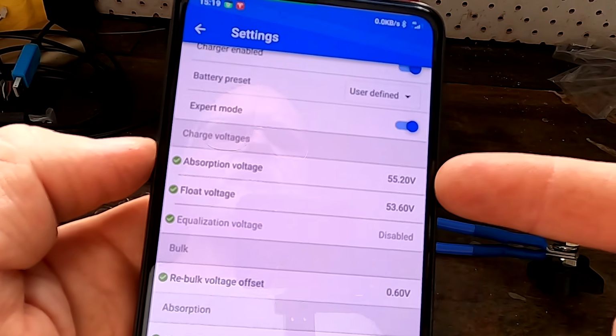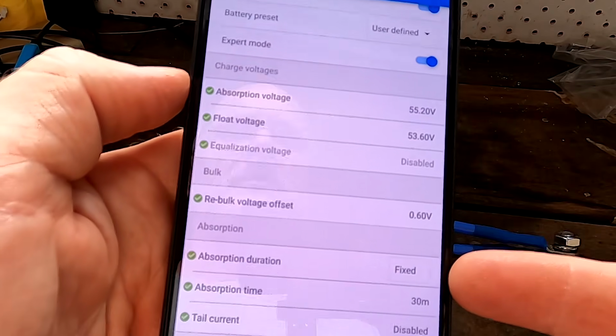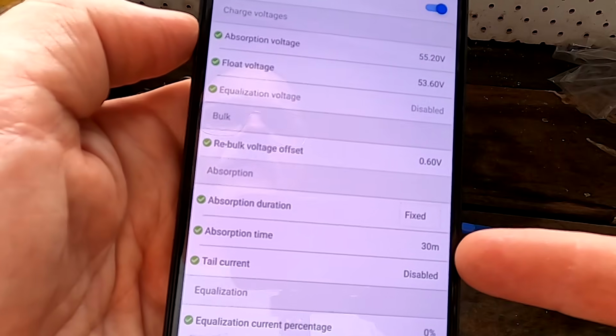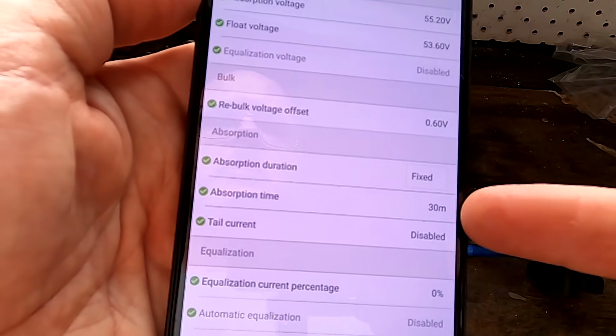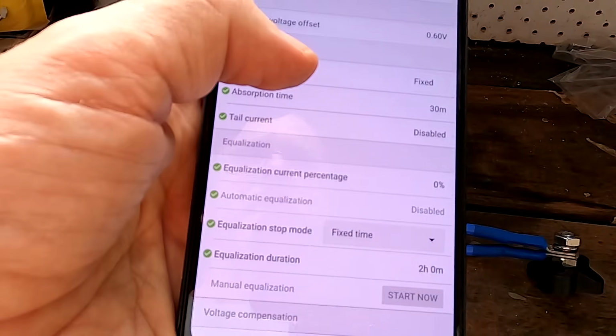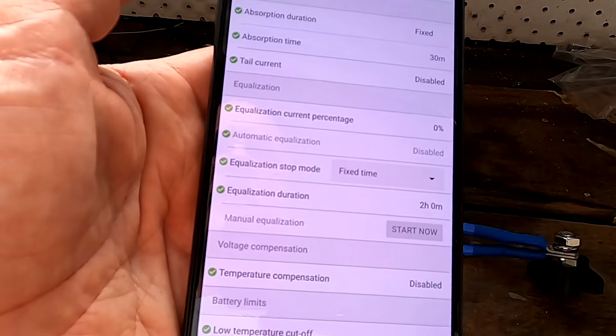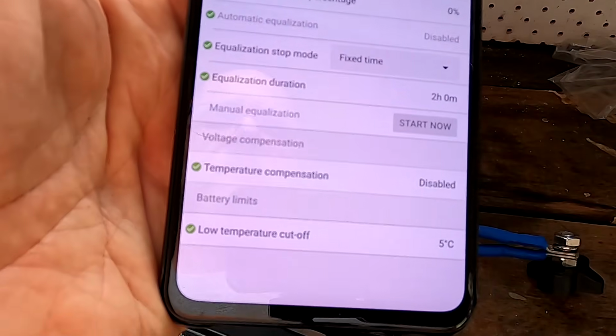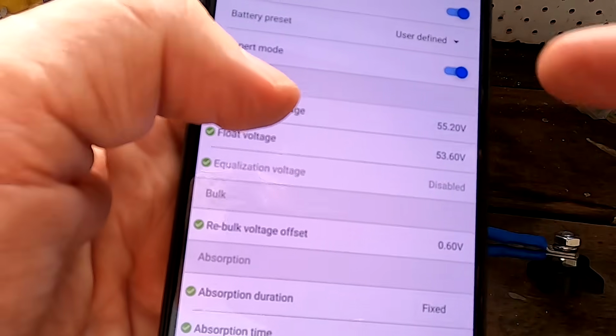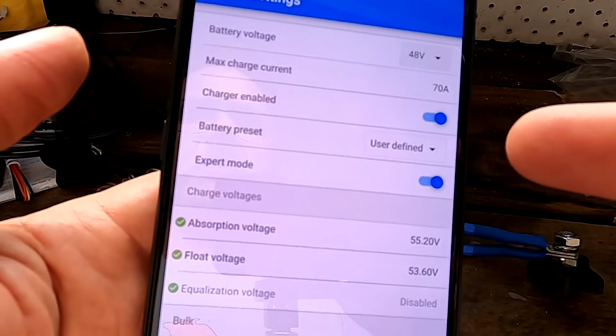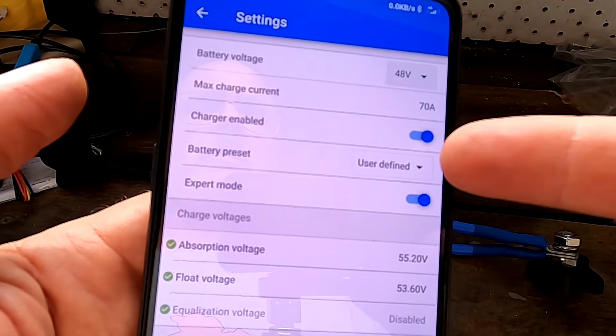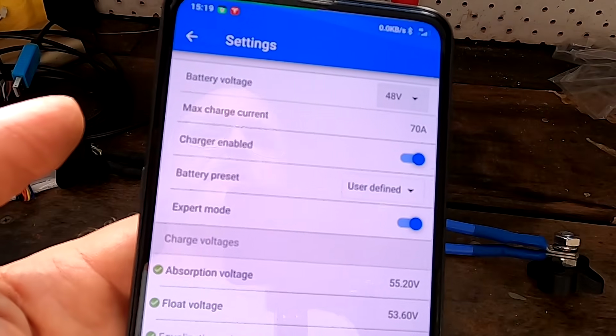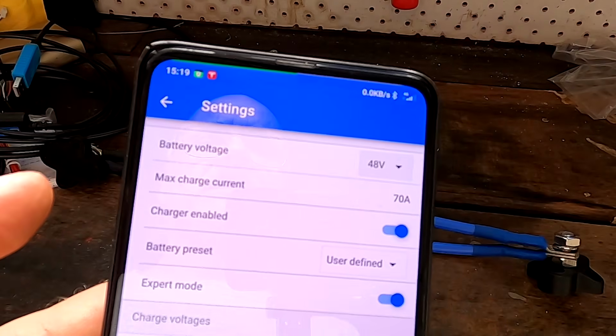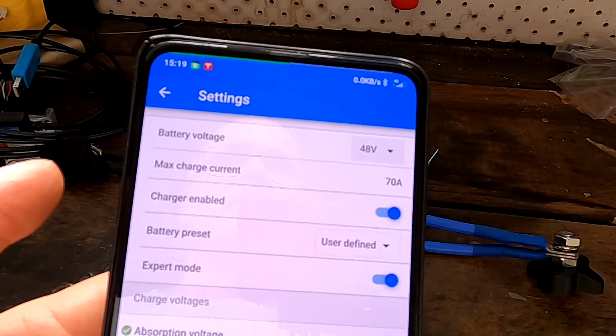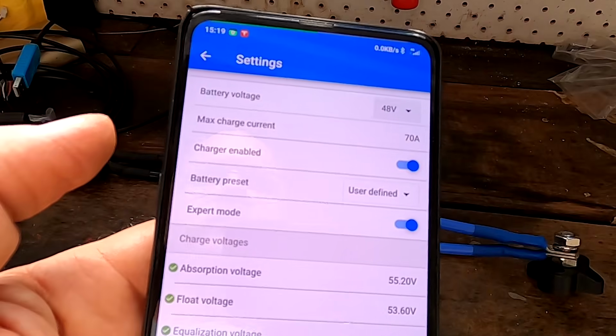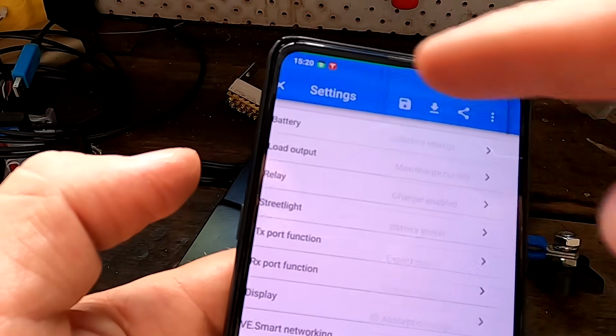So these are the settings I have: 55.2, 53.6, 0.6, and the absorption is fixed for 30 minutes. I don't use the tail current here because I want that 30 minutes to give the BMS time to balance, and everything else is turned off or not active anyway. Temperature compensation is already disabled. This is all set by pre-selecting the lithium iron phosphate profile. As soon as you change one parameter, it will say user defined, which is 70 amps into the battery for one controller at 48 volts. Yeah, so this is all good.